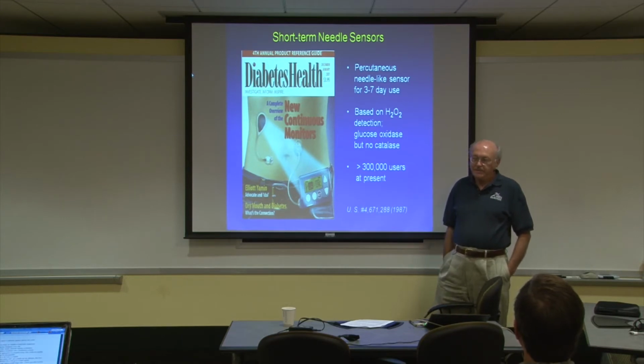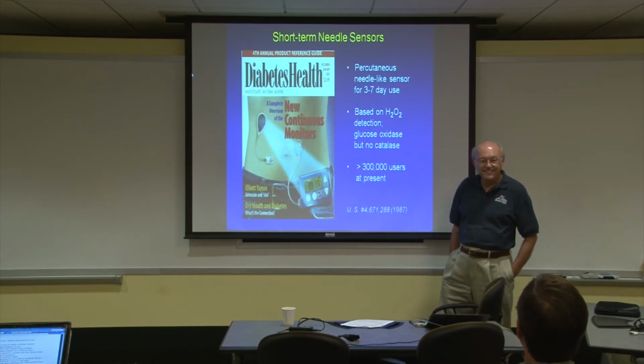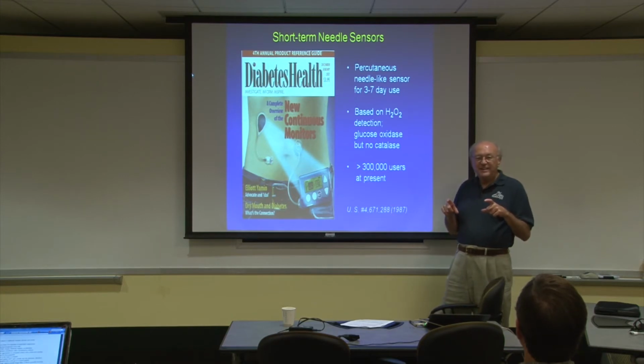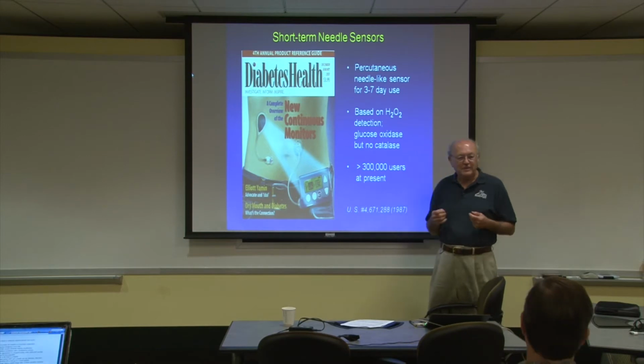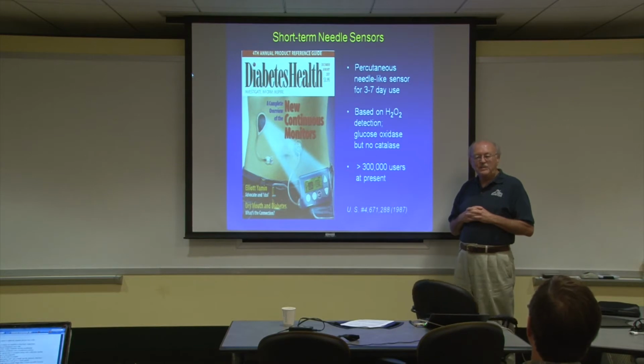Yeah, there was a big worry just recently because there's no instructions on what to do if the needle breaks. On the package insert, companies didn't put the instructions in there, so when the needle breaks off in place, some people try to figure out how to get it out, with whatever tool they have handy, making a big mess of everything. And the company that makes these failed to report these incidents to the FDA, right? So this is a big violation.